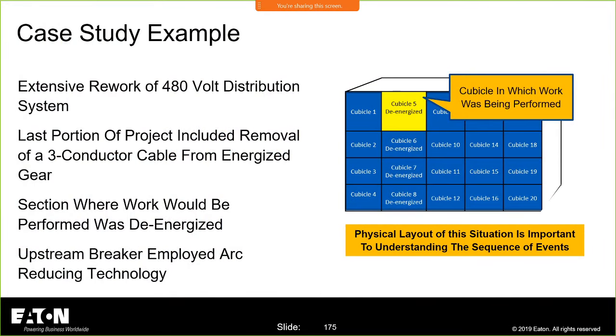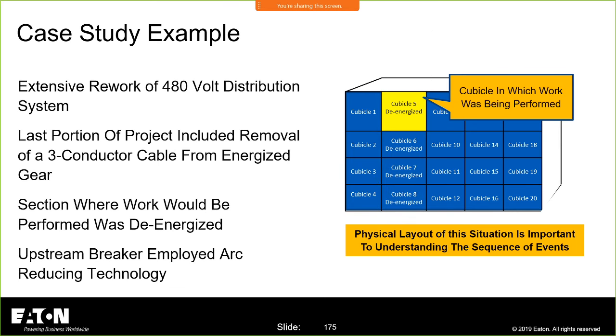There was extensive rework being done on a 480 volt distribution system. In the very last part of the project, which included the removal of 3 conductors from this energized gear, you'll see the cubicle that they were working in, and the key message here is that all of this equipment, so this cube, this line here and everything over here was all energized. Okay, this column was de-energized. So in this equipment, there's energized parts and pieces, right?